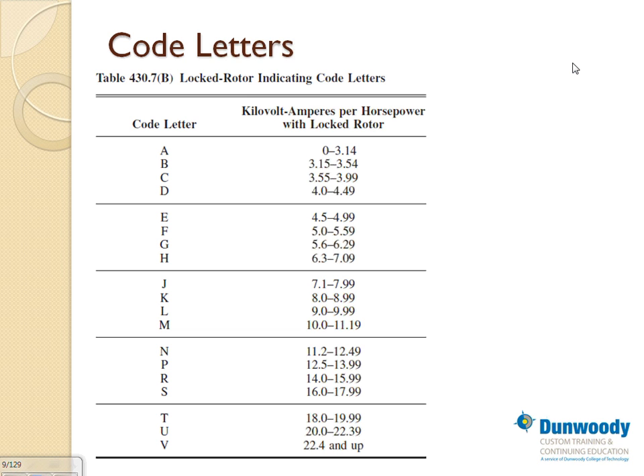There's the design letter and there's the code letter. The code letter is the inrush current. How much current when you start the motor? This motor is going to suck out of the system for only 10 seconds until it comes up to speed, if it's across the line. If it's a VFD, by the way, these will go way down, if you're soft starting it with a VFD or a soft start.